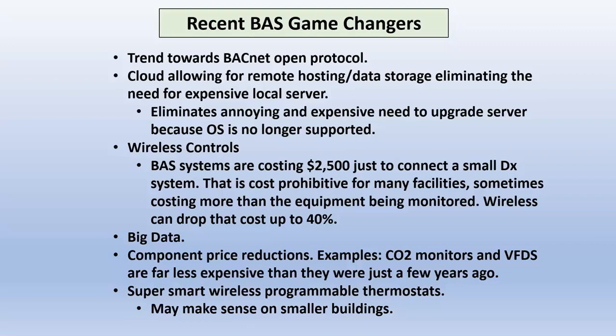Wireless controls, this is a total game changer. BAS systems are costing $2,500 or so just to connect to a small DX system. You might pay more to connect the BAS system than the small system actually costs. If you use wireless, you can drop that install cost 40%. You don't have to pull wire, run conduit, all that labor you can wipe out. And they've gotten much, much more robust with the wireless mesh technology, which uses every different device as a stepping stone for the one before it. So they're all tied together. They're a self-healing network, sometimes they're called.